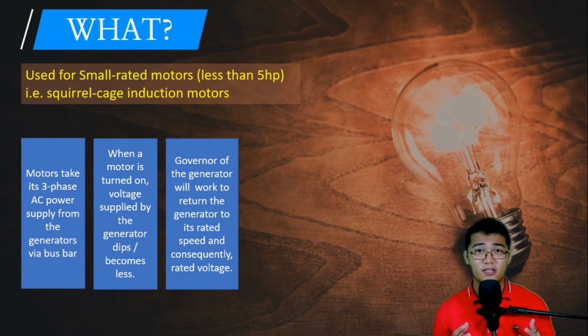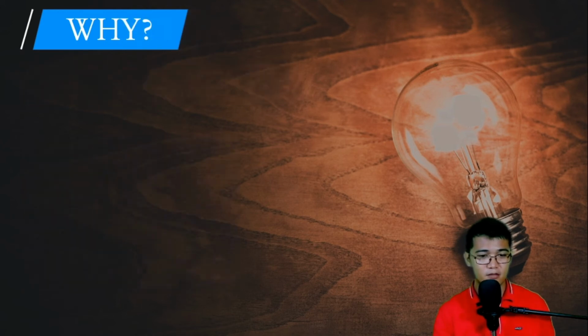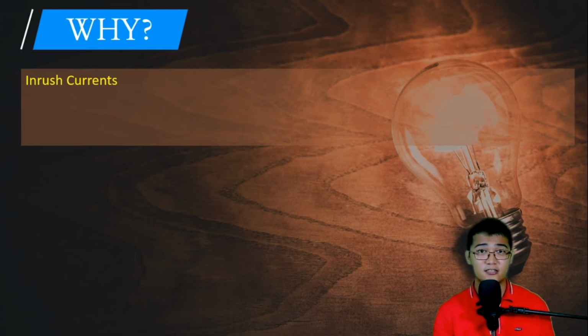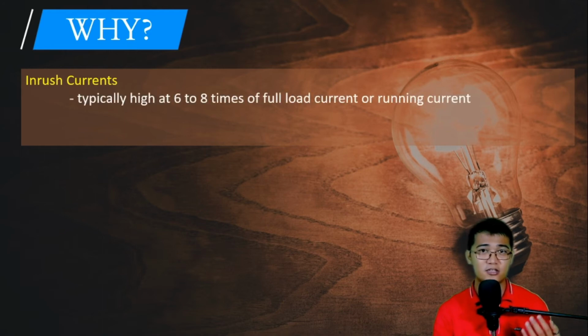Now, this is the reason why direct online is only applicable for motors that are small rated. Yung mababa lang yung rating. It's because for larger motors, mas mangangailangan na ng high starting current. And actually, in technical terms, we call these currents inrush currents. Yung starting current na binabanggit natin kanina is inrush currents. These currents are actually typically high in value, 6 to 8 times that of the running current.